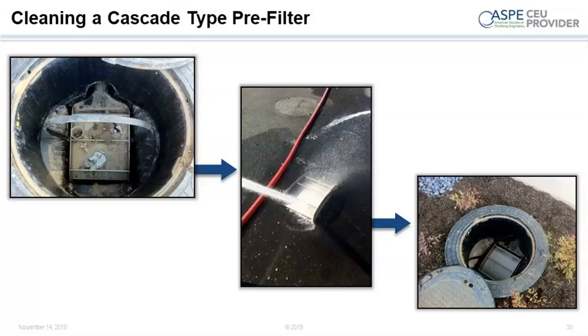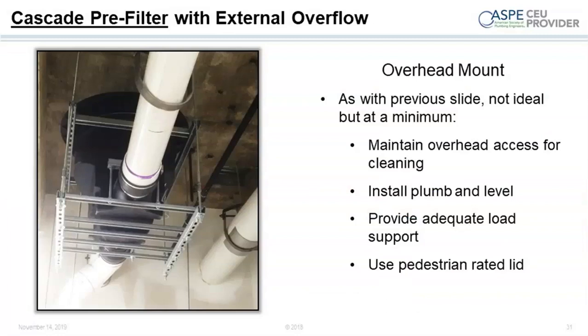If you're in a dry part of the country where you're going to have dust, consider first flush diversion — diverting approximately an eighth of an inch or a few millimeters of rain off the structure before it reaches the inlet pre-filter. That's really the only effective way to remove very fine material. You'll need an automatic means of diverting the water after a certain amount flushes off. This is especially true in western states where very fine material builds up over months of no rain before the first rain event. We've got lots of great questions, but I need to speed up to cover the primary equipment.